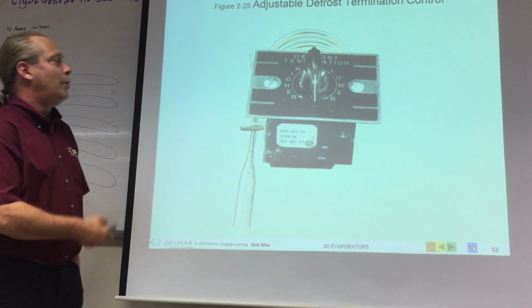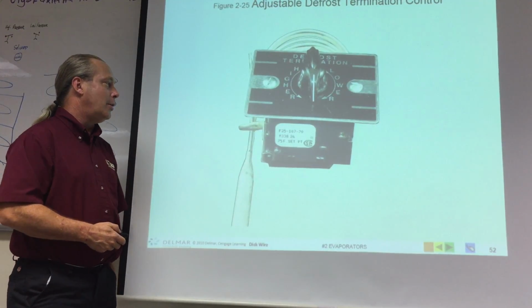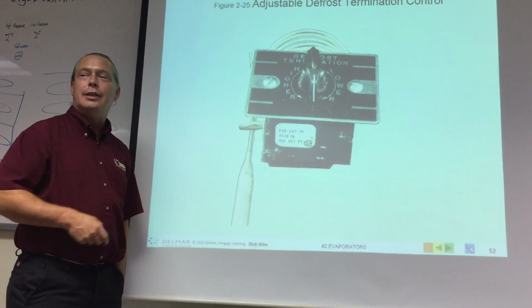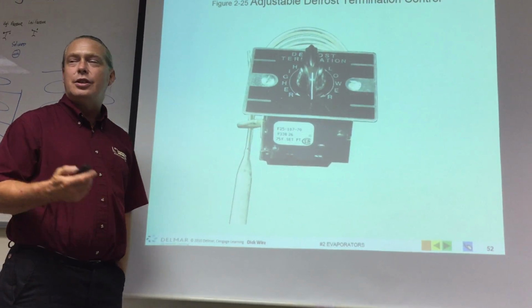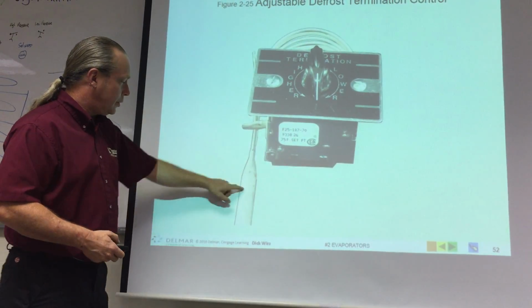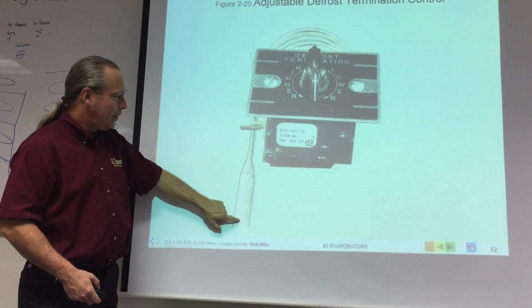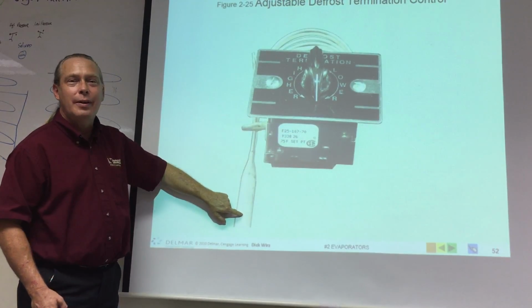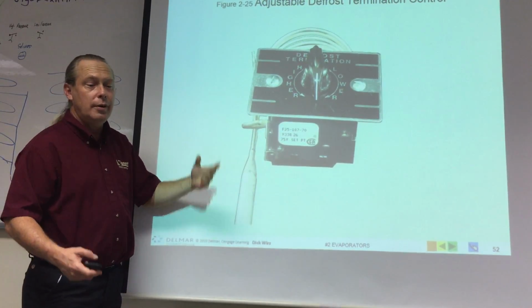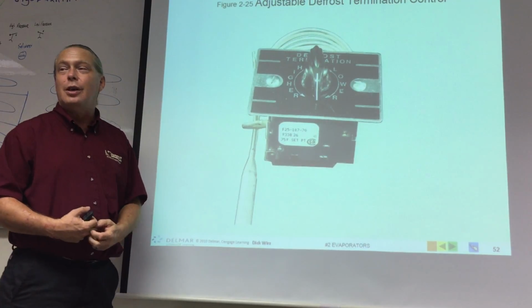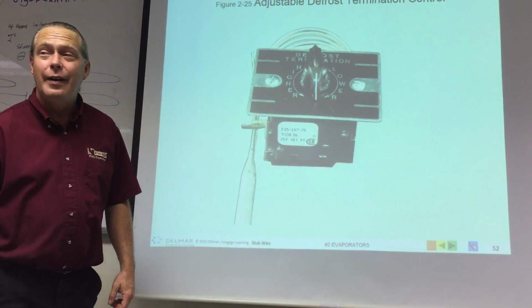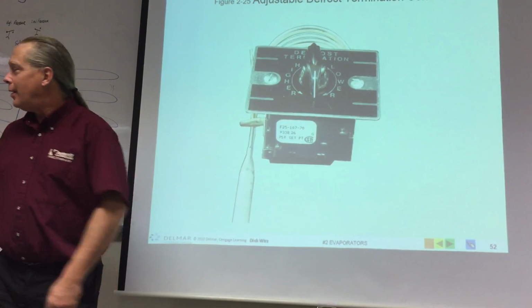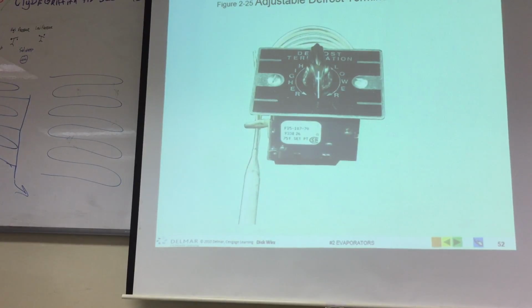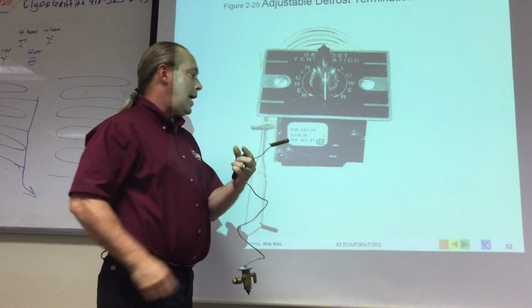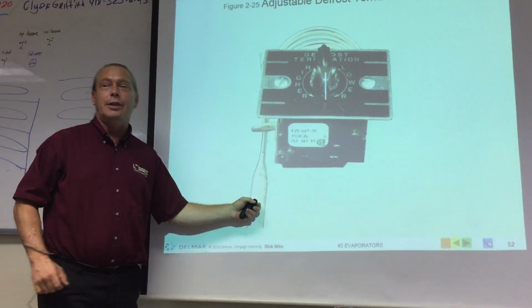Here we have an adjustable defrost termination control. I think I would have liked to see inside that more, but it's just a thermostat. That's all it is. And you'll notice the adjustable one. What do you figure is in this bulb? Maybe, but it would be some sort of gas. What's in this bulb? Refrigerant. Refrigerant's in that bulb. So some sort of refrigerant is in this bulb.